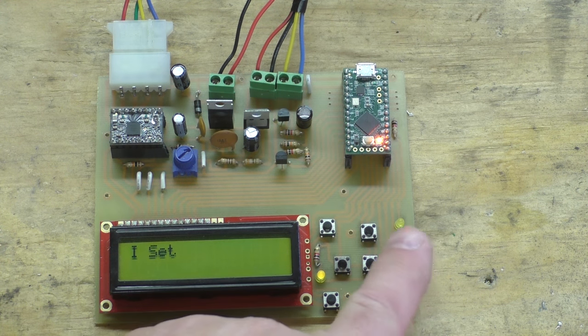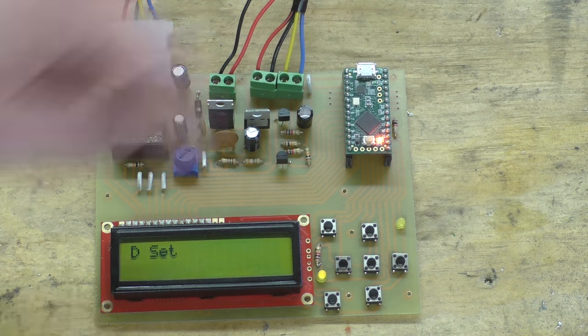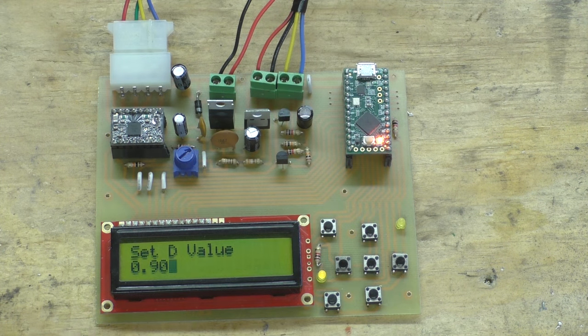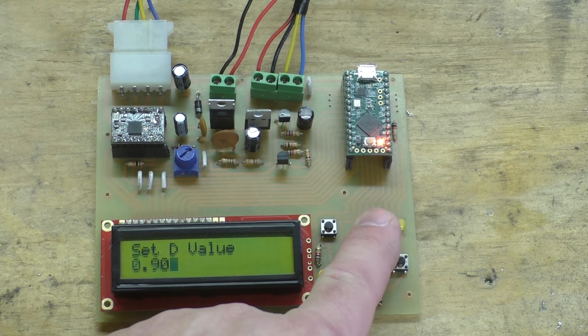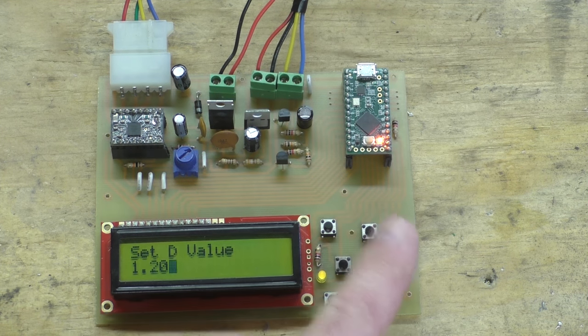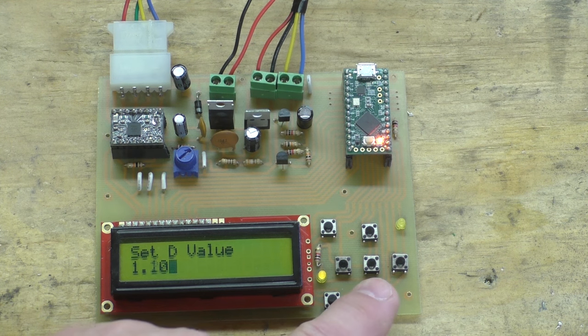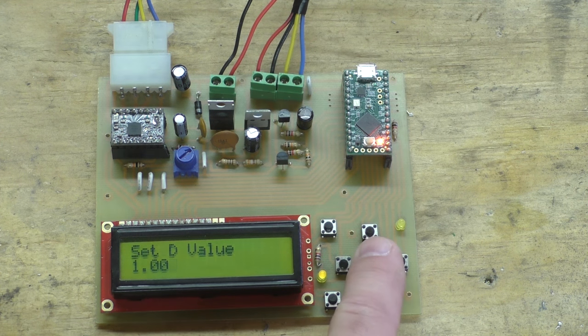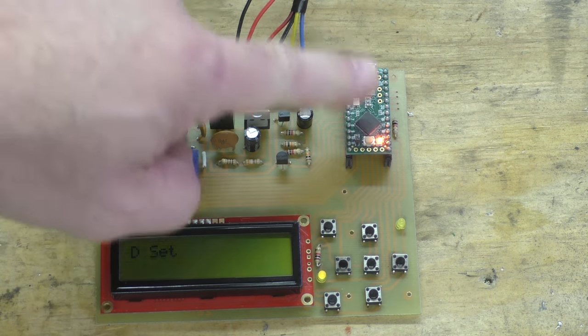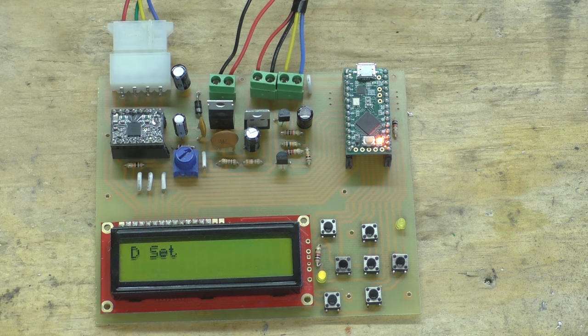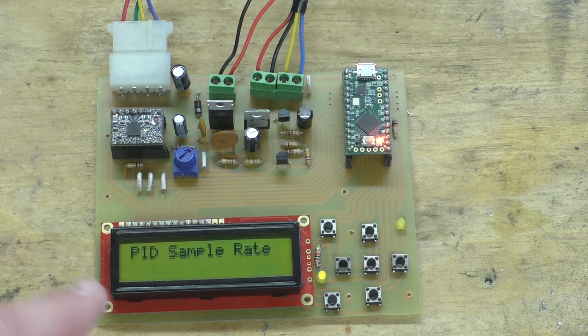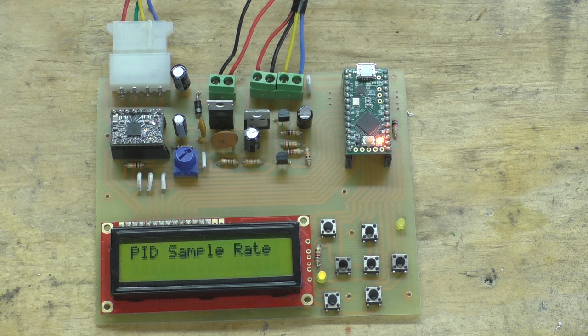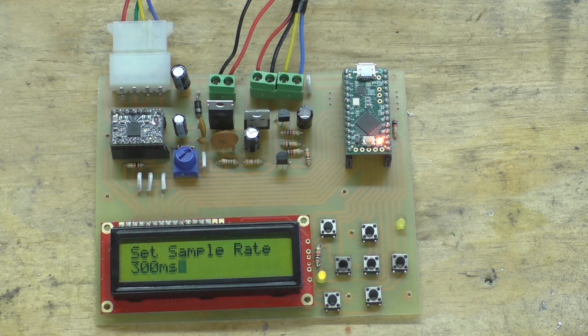And this just sets a set speed on the puller roller that doesn't change. It doesn't do anything with the PID algorithm, there's no error correction. This is just so you can start it up and run your extruder and get everything set up and going before you go into automatic mode. Next are the PID parameters - there's a P, the I, and the D, and these are all set the same way. You hit the enter button and you can change the values.